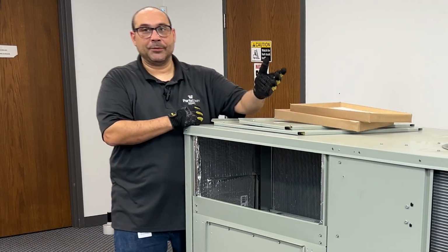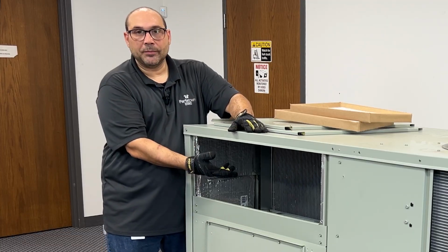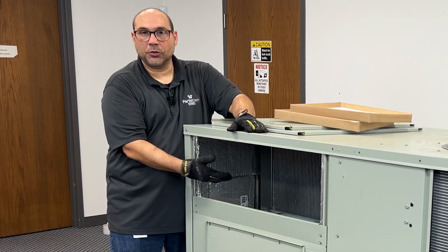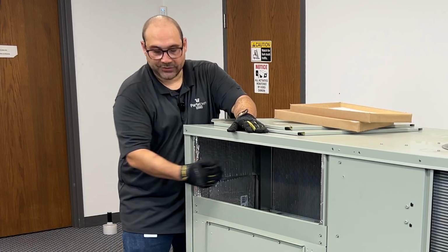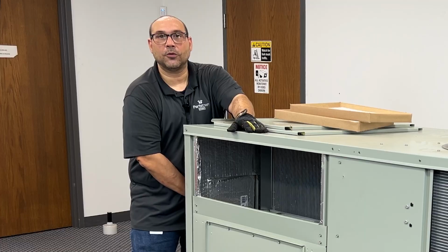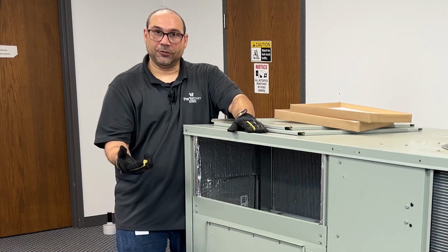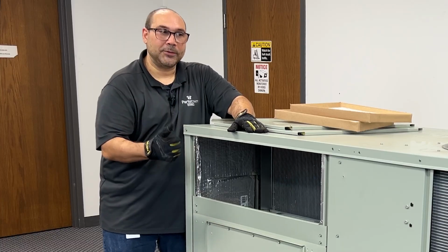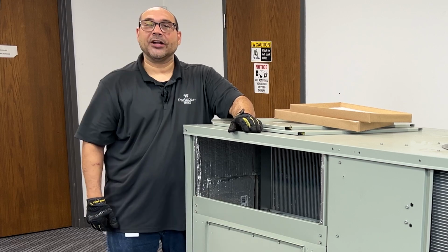All right, another common place for a refrigerant leak is going to be the evaporator coil. This is going to be behind the filters. So just like you're going to replace your filters, you go in the same compartment, and you're going to be looking for the same types of things you're going to look for on a condenser unit. Discoloration, oil. If you do find that, spray the soap bubbles with 300 psi of nitrogen in the system, and you can go about your repair.